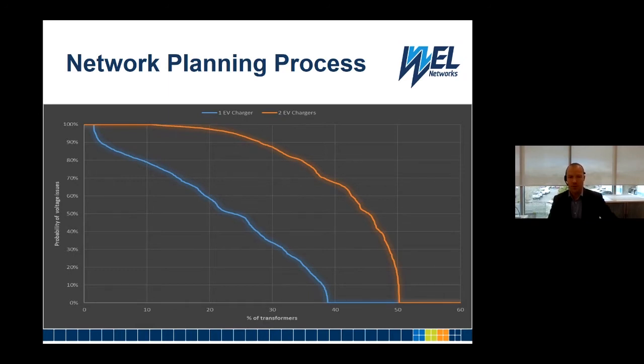We can see that this curve says that of this 10 or 20% of our transformers, they're definitely going to require an upgrade if they have two EV chargers on them. And then it tails away - one EV is a similar curve.